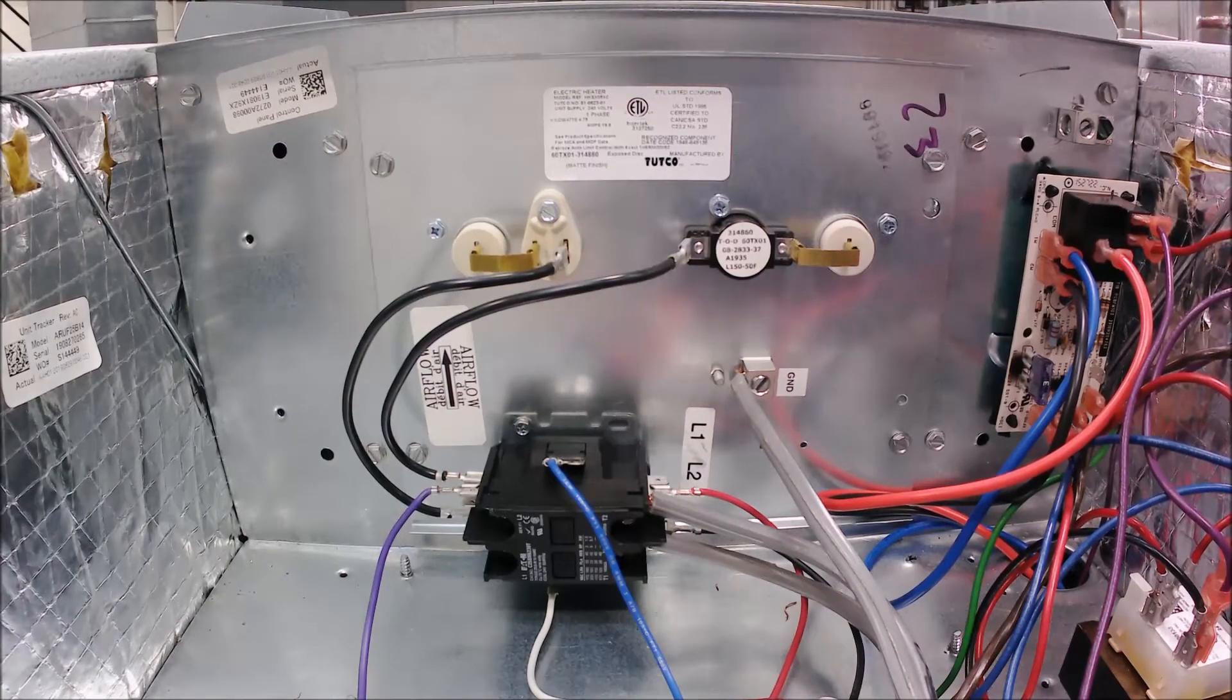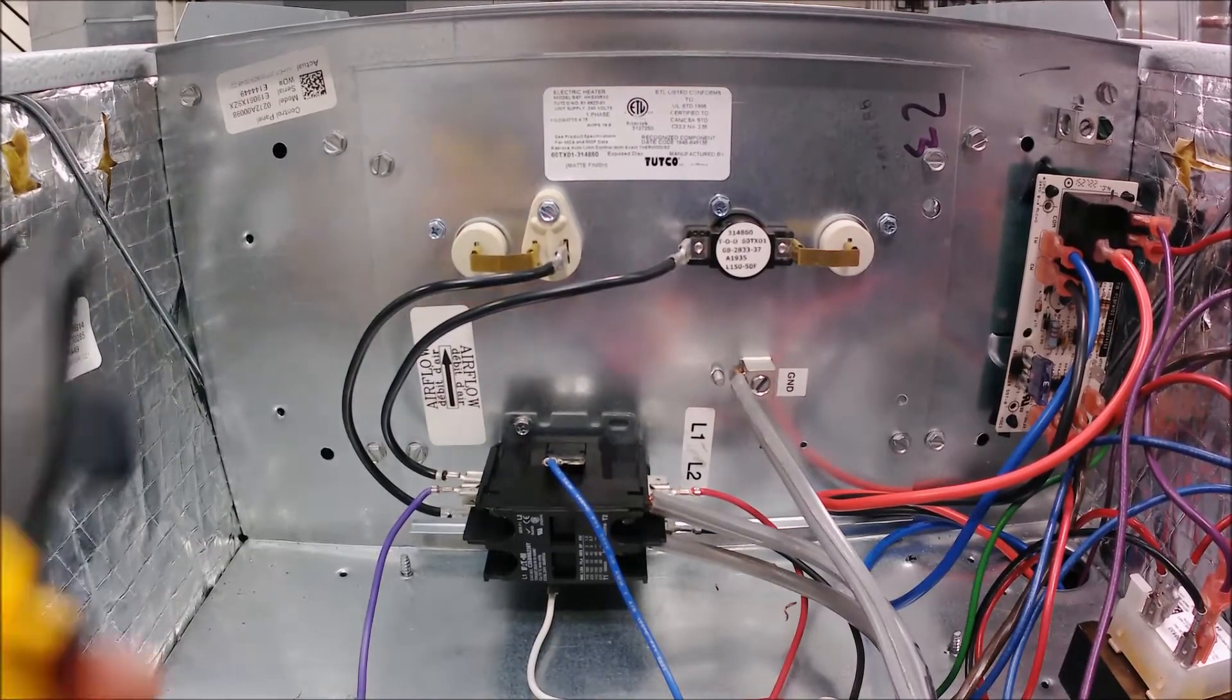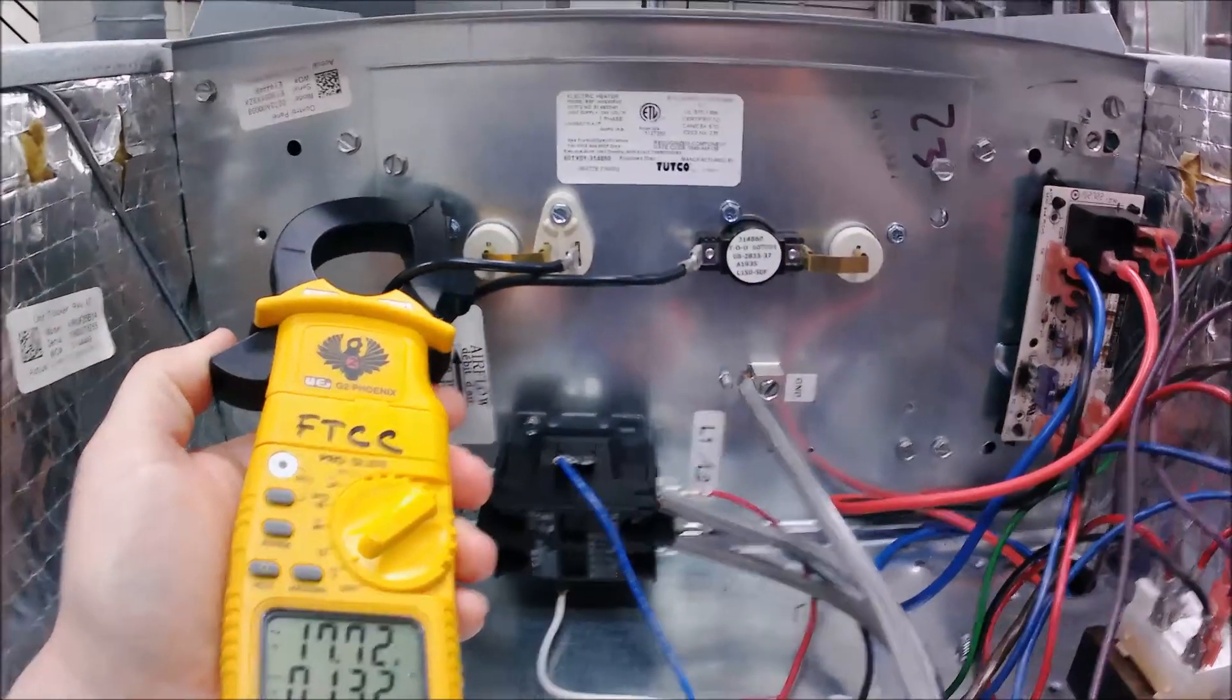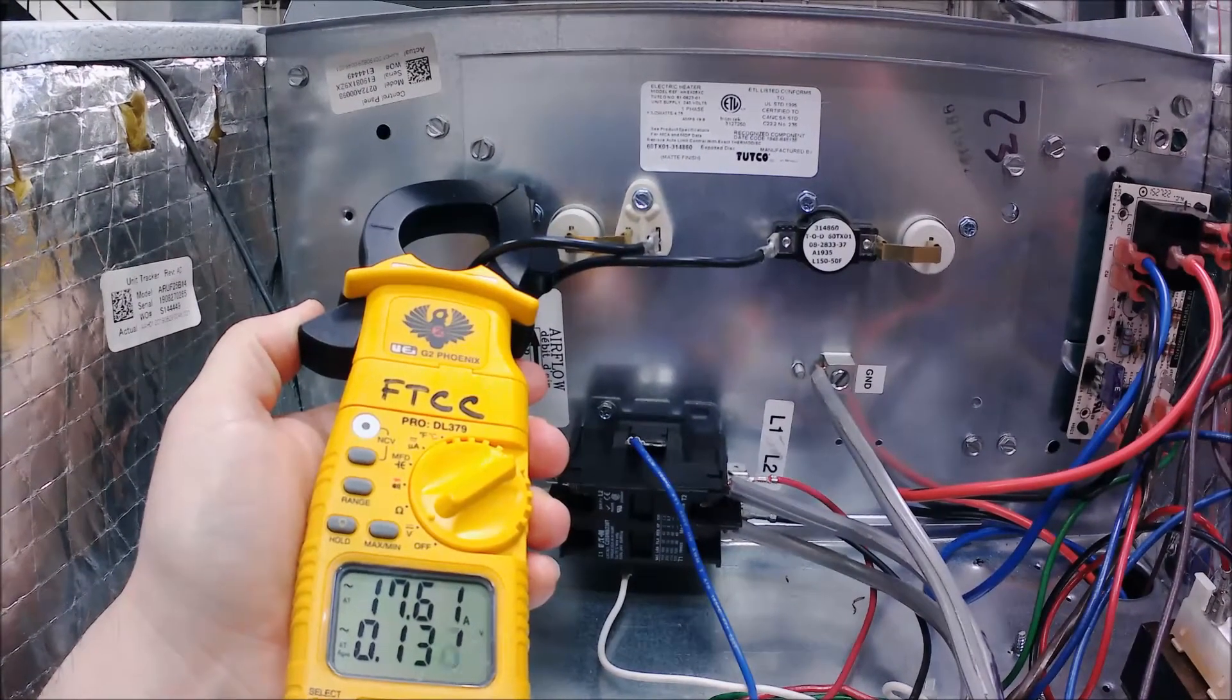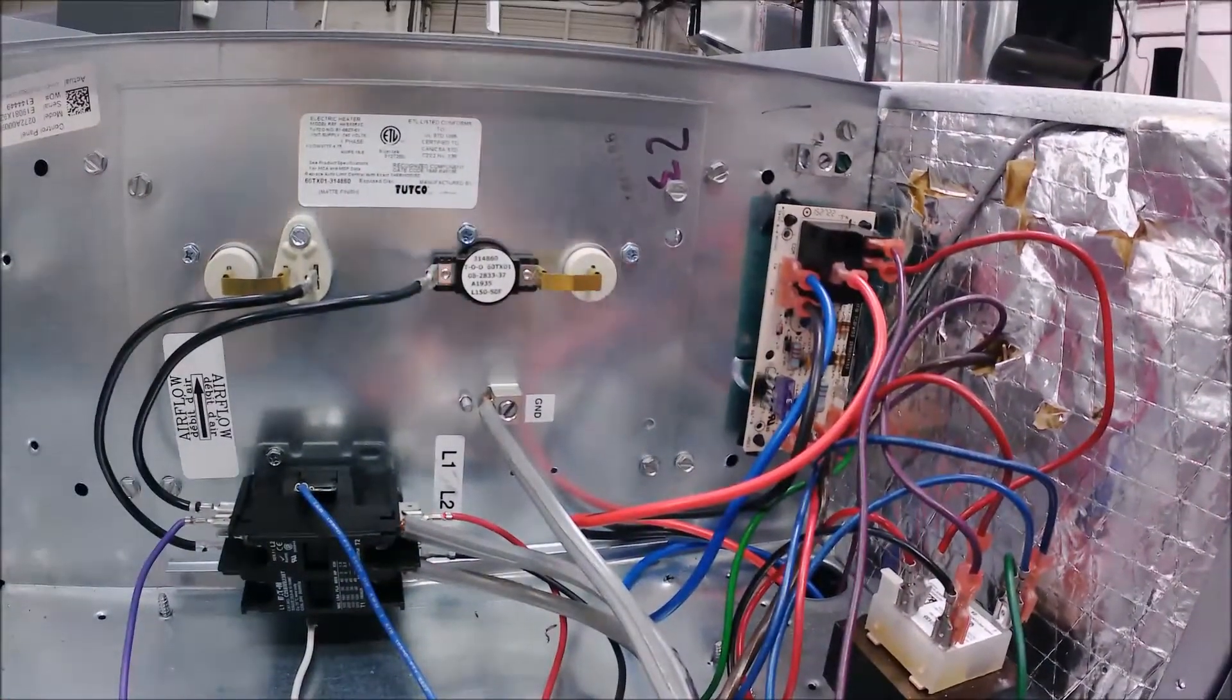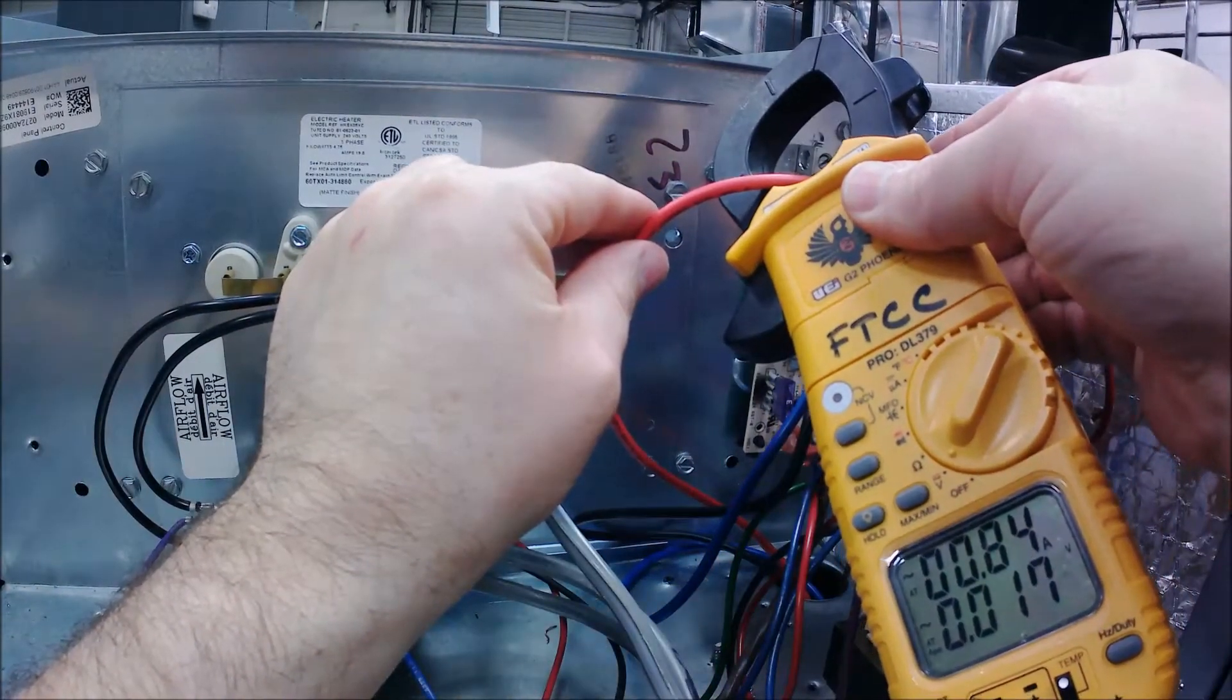All right, there goes our heating elements. Simple amp draw - you can see down there at the bottom we've got about 17 and a half amps on that one heating element. This is a simple 5kW heat strip. If I were to check the amp draw on the fan, you're looking at about almost one amp.